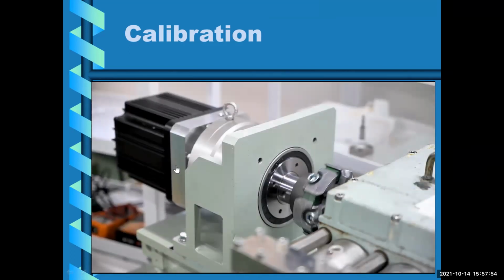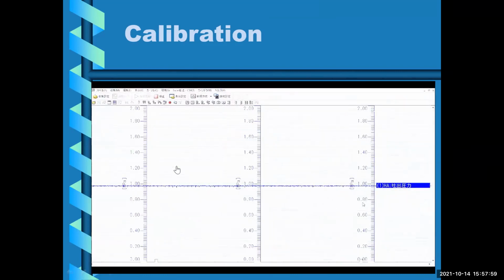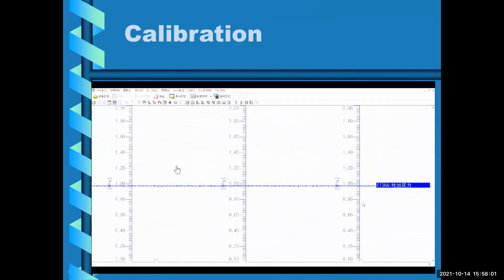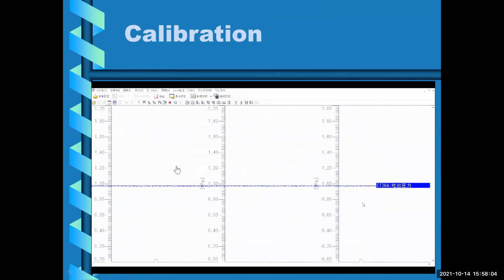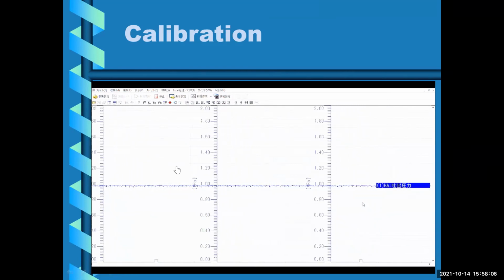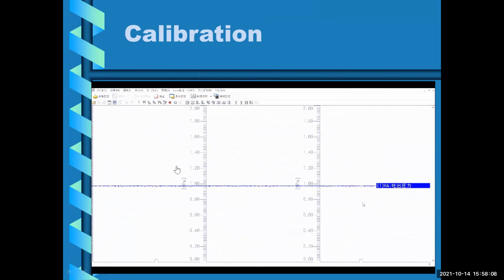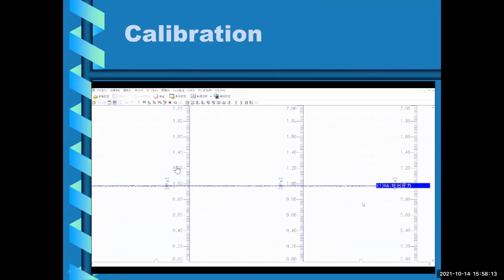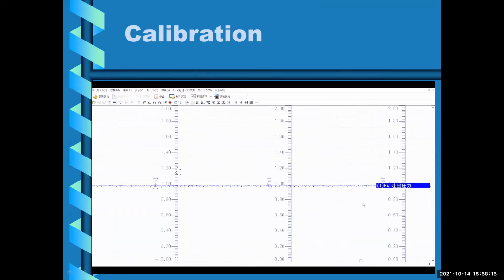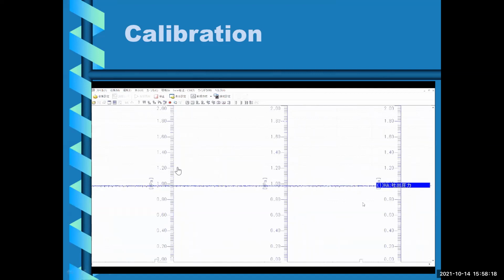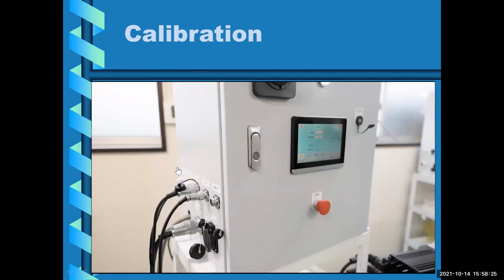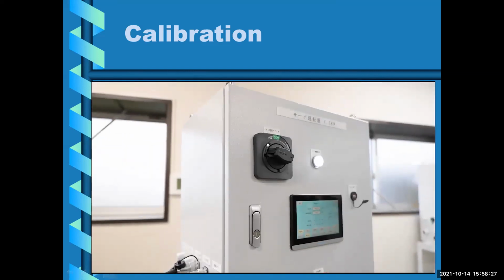Here is the adjustment of the motor speed. As a result, the fluctuation of pressure after calibration is very marginal, very small. Please note, the fine adjustment of the motor speed is viable with our pumps because the pulsation generated by our pump is very marginal to begin with. Otherwise, fine adjustment of the motor speed would be very sensitive to the motor.